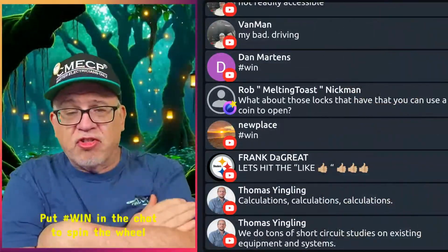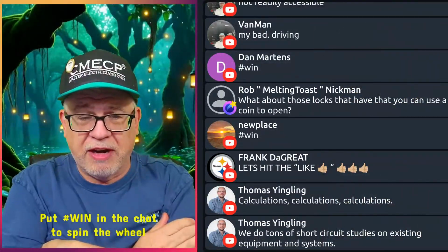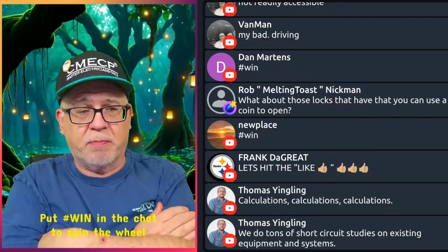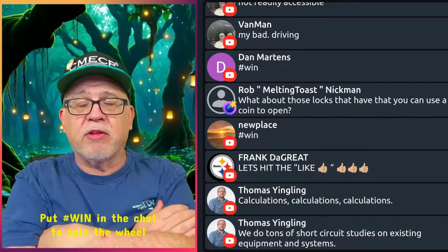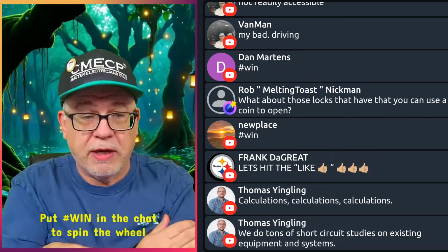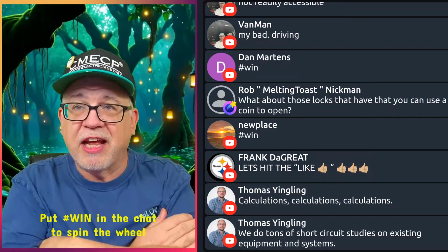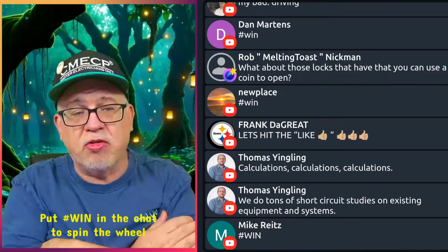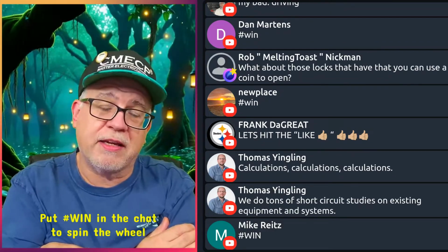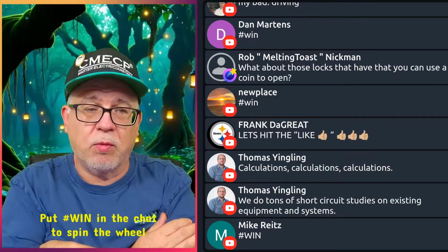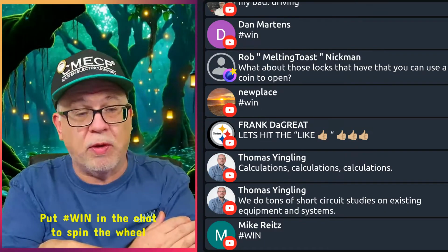Check this out. You have circuit breakers that are straight rated, and you have some that are slash rated, okay? Like a breaker that's rated 120/240, it's telling you that I can use it where one leg connects to ground, on 120 volt circuits as well as 240 volt circuits.